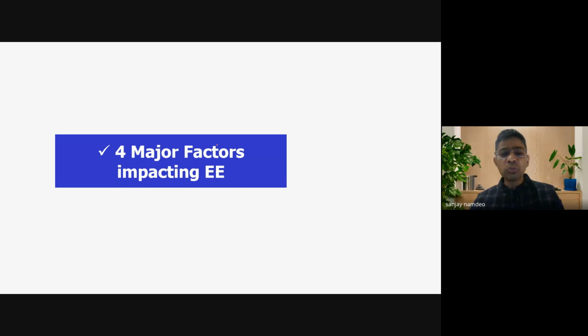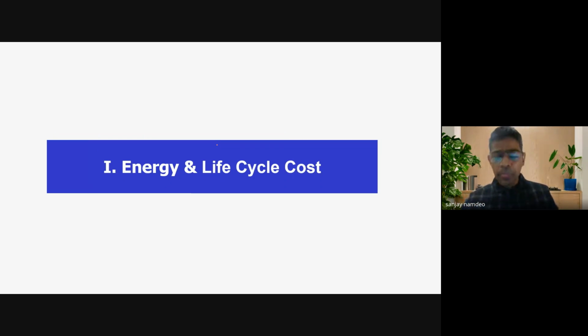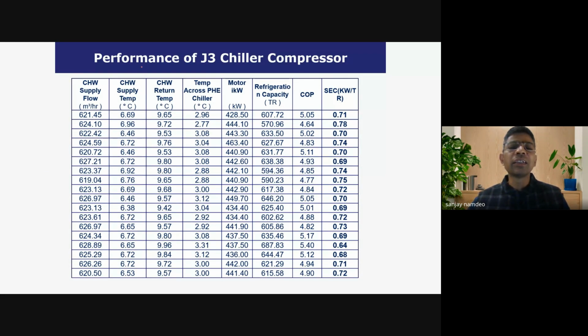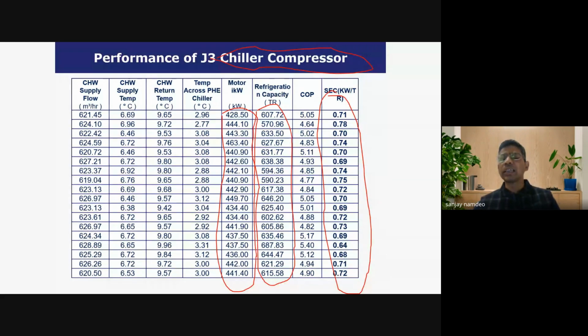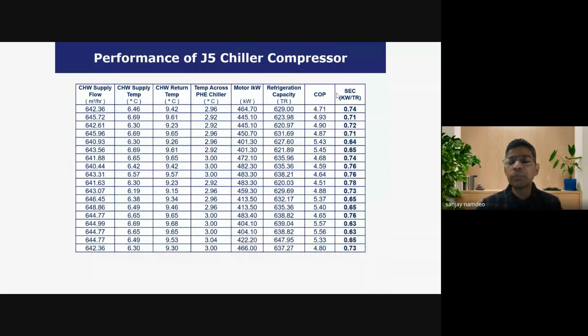So quickly, I will take you through the 4 major factors which impact energy efficiency in, let us say, an organization, or it is applicable to most of the industry or the institutions. The factor 1 is the energy and the life cycle cost. So this is a performance parameter of a chiller, which was audited some time back. So here you can see this chiller is of around 615 TR it is generating. This is the actual power consumption. And here you can see the specific power consumption, that is kilowatt per TR, how much this chiller is consuming, right? Similarly, this is again the performance of a different chiller, that is J5 chiller of the industry, right?